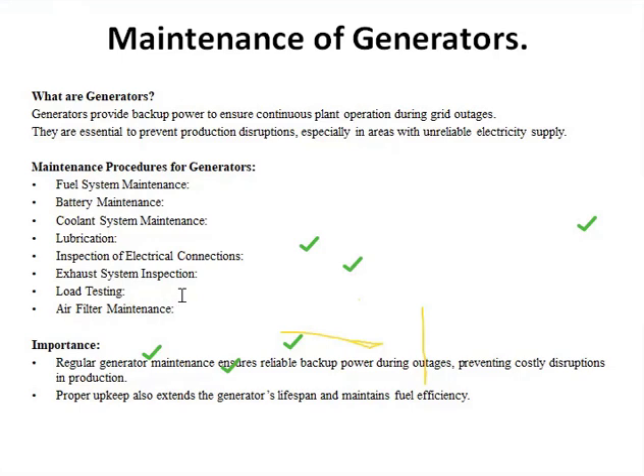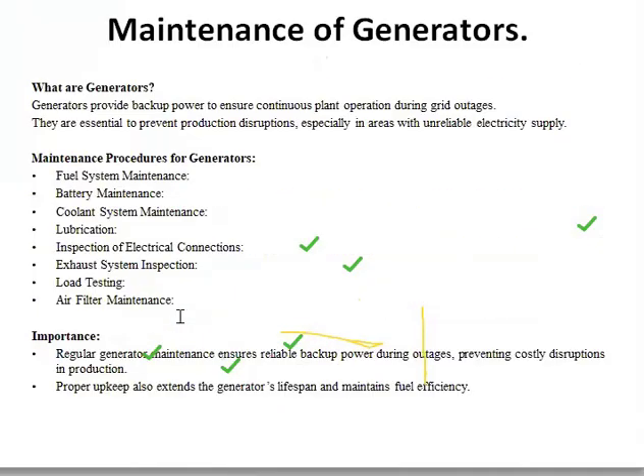We also do load testing. We make sure that the generator can run the plant under load, to ensure that it can handle the plant's power demand. For example, testing our 400 volt generator under load simulates actual conditions and confirms that the system can run the plant. I also do air filter maintenance. We replace the filters and clean them during maintenance. Regular generator maintenance ensures reliable backup power during outages, preventing costly disruption in production. Proper upkeep also extends the generator's lifetime and maintains fuel efficiency.